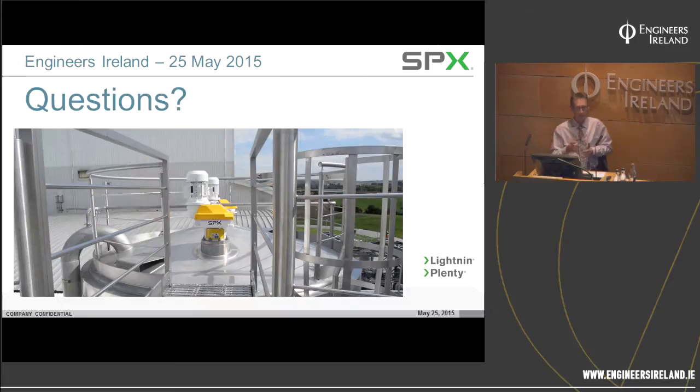And with a long shaft, once you start to worry about critical speed and bending moment, you've either got to have a steady bearing in the bottom of the tank, which most people don't like, or you've probably got to over-design the mixer. And that means you might be going from a 50mm shaft to a 75mm shaft. And then, by the way, the gearbox you've chosen for torque won't take a 75mm shaft, so you have to go to the next gearbox size up. So everything starts to escalate, and you can quickly find you've doubled the price of the mixer compared with what it would have been if you'd had a more appropriate batch geometry. Yeah.